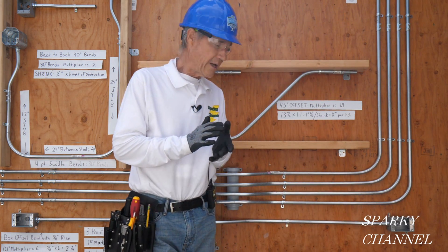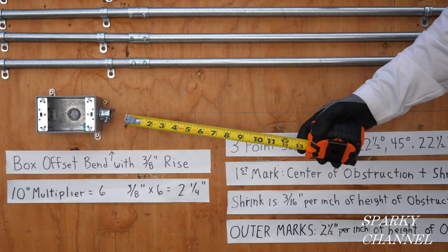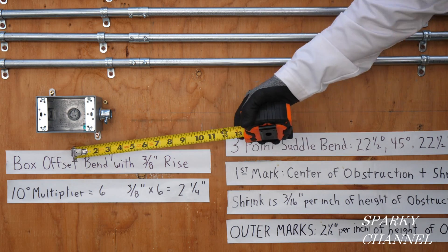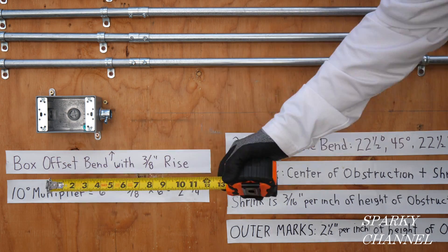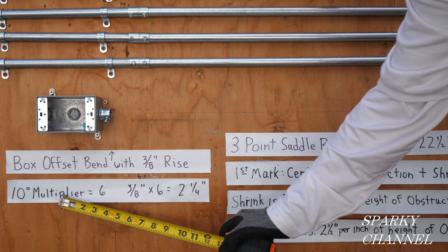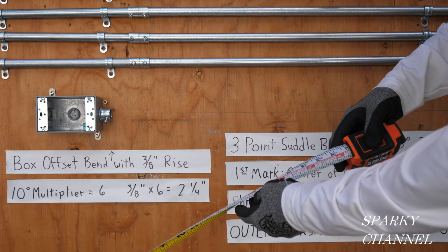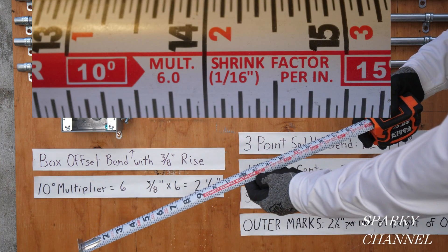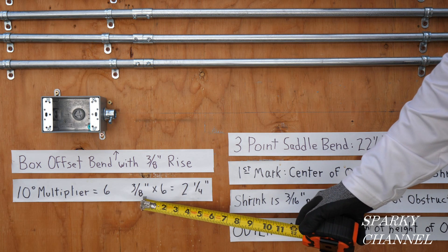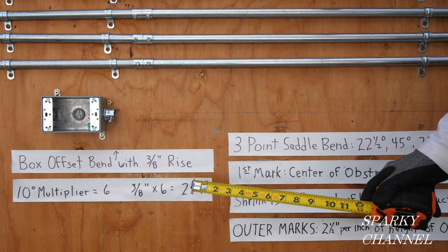I'm going to take this down and bend up another one to show you how to do it. I've taken my conduit off the wall and the first bend we're going to make will be the box offset bend. This box offset has a 3/8 inch rise and 10 degrees, because we're going to make two 10-degree bends. The multiplier for 10 degrees is 6 — you can find that on the back of this Klein tape measure, which has conduit bending multipliers. So you take the rise, 3/8 inch, times 6, equals 2 and 1/4. We're going to have 2 and 1/4 inches between our bends.